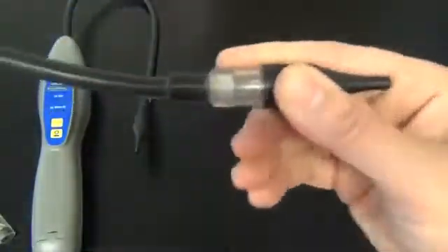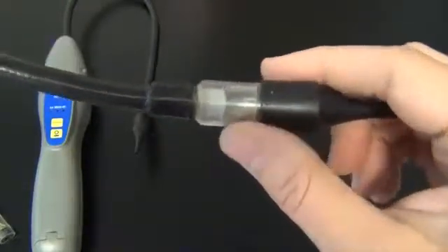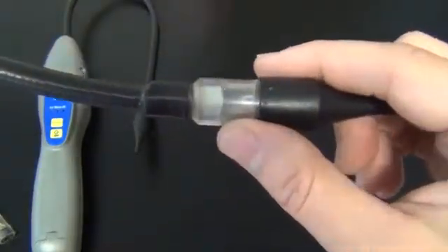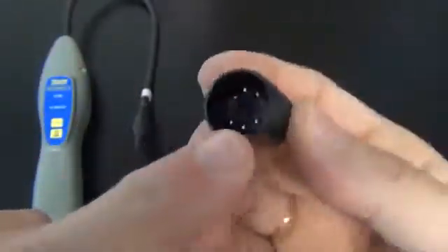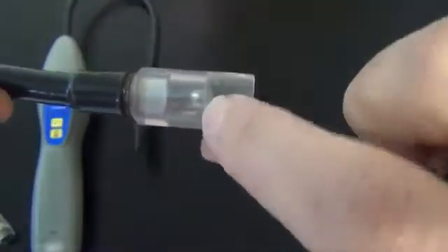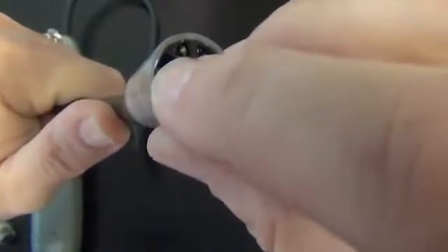In some of the older original Acuprobes only, 2005 and older, there is this type of sensor. The sensor itself has a dimple. It does not have a key slot. The end does not have a raised key slot. What it has is a white line that's built into the filter tip.